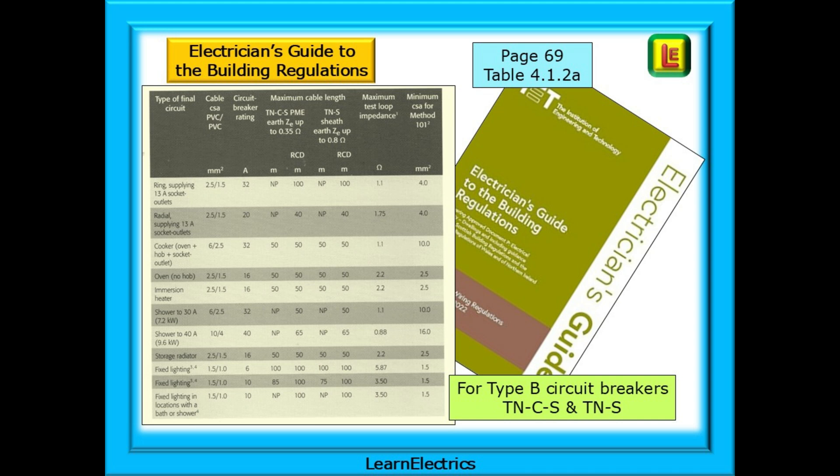If you have the Electrician's Guide to the Building Regulations, shortened to EGBR, take a look at Table 4.1.2a on page 69. Here is a table that shows all the common breaker sizes with data for Type B breakers, including cable sizes, circuit lengths, and most importantly for us, the maximum ZE for TNCS and TNS systems and the maximum ZS values. We can do something with these figures.